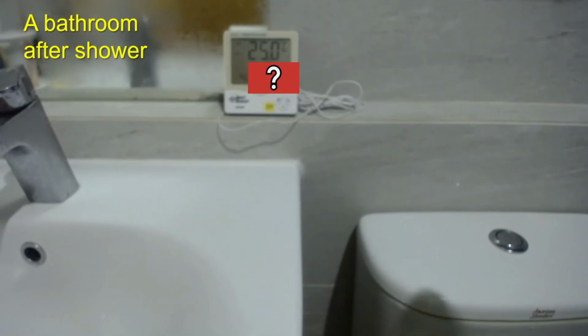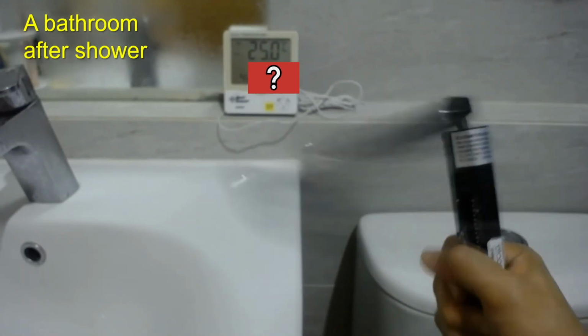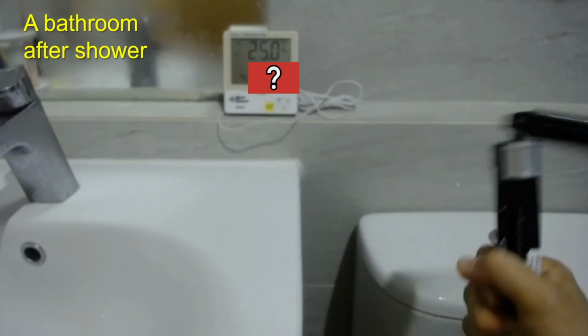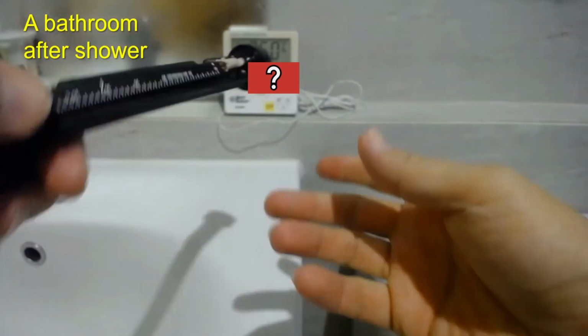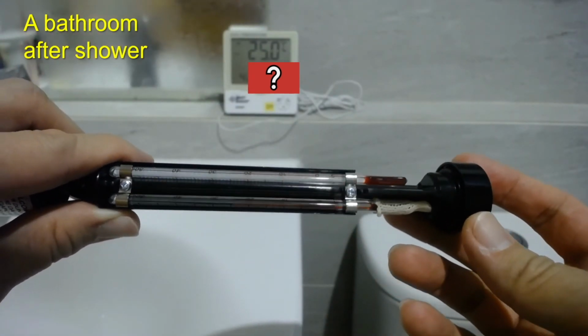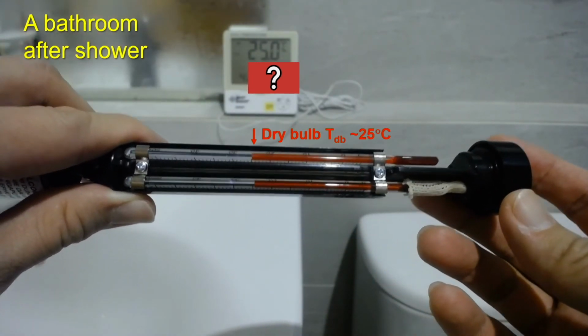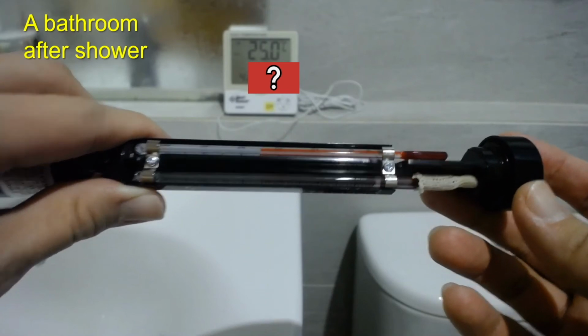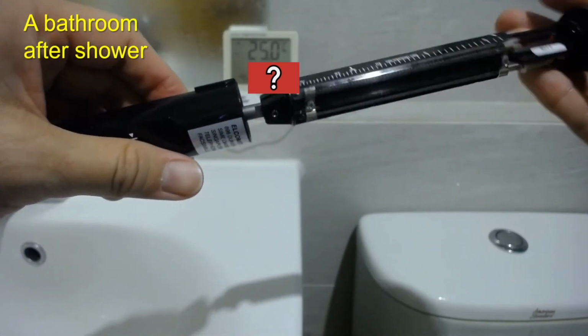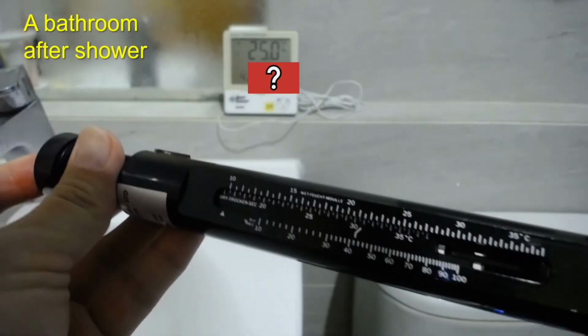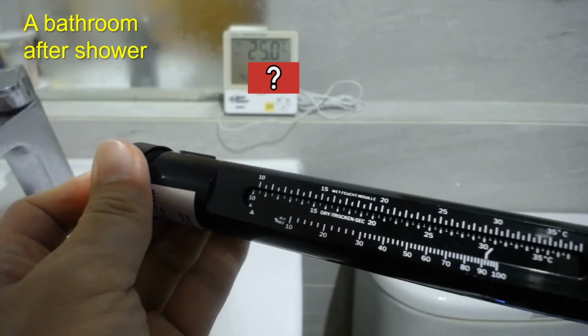What if we have another room condition, like the one in a bathroom after taking a shower? Using the Sling hygrometer, we can find out that the dry bulb temperature is 25 degrees Celsius and the wet bulb temperature is 24.5 degrees Celsius. The temperature difference between the two thermometers is much smaller here because relative humidity is higher in this case.